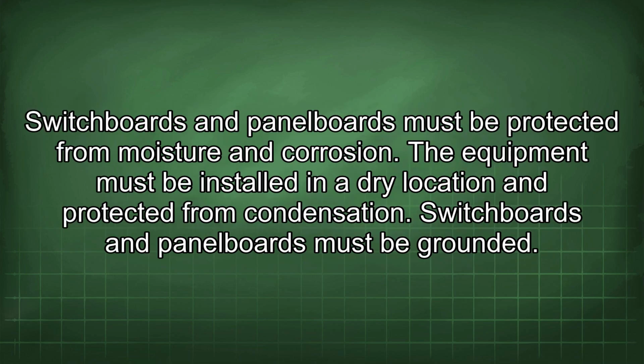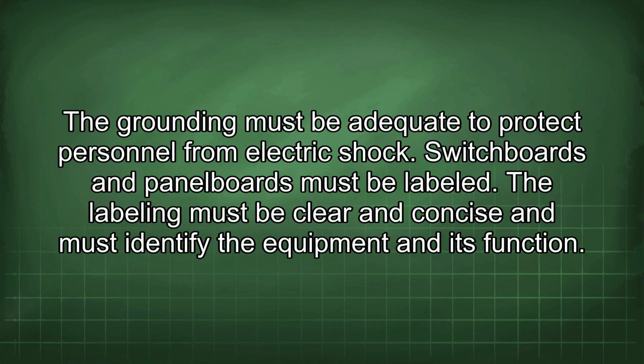Switchboards and panel boards must be protected from moisture and corrosion. The equipment must be installed in a dry location and protected from condensation. Switchboards and panel boards must be grounded. The grounding must be adequate to protect personnel from electric shock. Switchboards and panel boards must be labeled. The labeling must be clear and concise and must identify the equipment and its function.